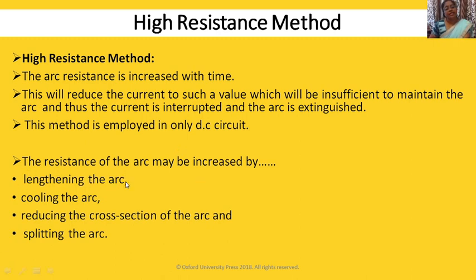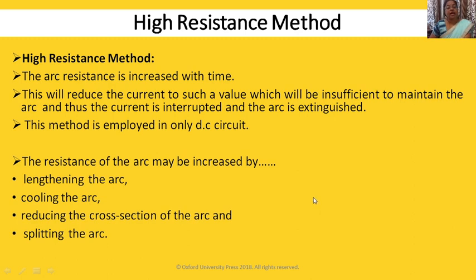What is lengthening the arc? As you know, R = ρL/A, which means resistance is directly proportional to length. In the high resistance interruption method, we have to increase the arc resistance so that the current flowing through it reduces to a minimum value. This is done by lengthening the arc — if you increase the length of that arc, resistance will increase and the arc gets extinguished.